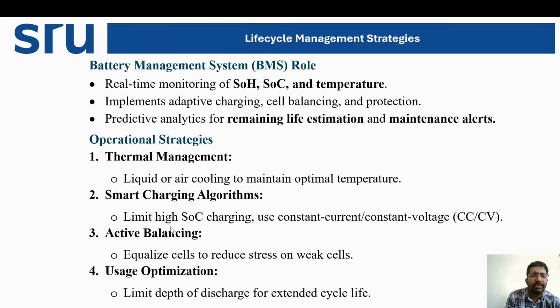Smart charging algorithm: which charging algorithm will be used for maintaining this? Limit high state of charge charging, then use constant current / constant voltage charging. Initially a constant current is used and voltage gradually increases, and once charge goes beyond 80%, constant voltage is maintained and current is slowed down. That is the CCCV, constant current constant voltage, charging mode.